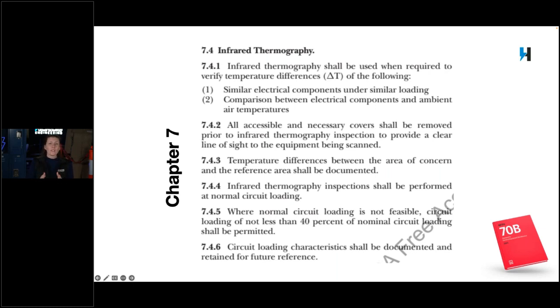All accessible and necessary covers shall be removed prior to infrared thermography inspection to provide a clear line of sight to the equipment being scanned. In other words, taking a scan on the outside cover doesn't really do you much good. You have to be able to actually see the electrical components, not just the case that holds them.